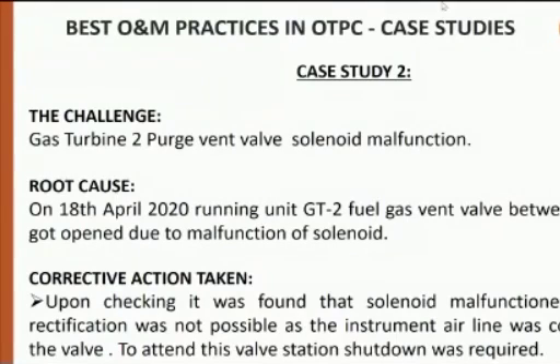Now this condition has resulted in circumstances where we have to go for a shutdown of the plant, and a shutdown of the plant costs very much in terms of heat rate, increased auxiliary power consumption, and basically obstruction to the supply of power. So we thought of a method to attend to this solenoid online while the machine was operating. This purge valve is installed between the SRV and the GCV. SRV is the speed ratio control valve, and the GCV is the gas control valve, so it sits between two important valves.